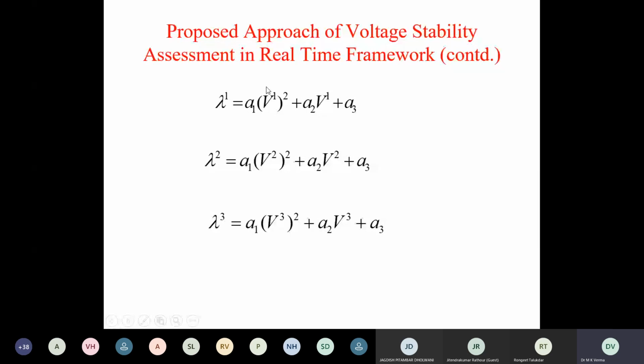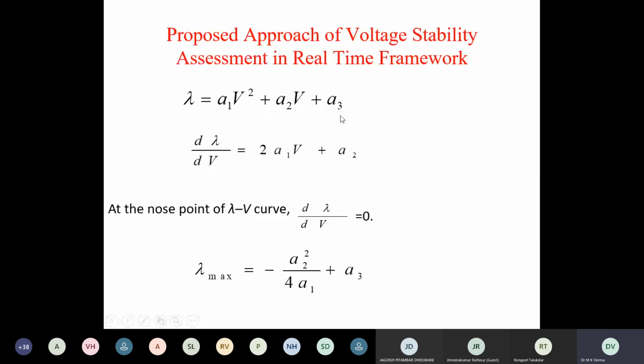Once these voltages V1, V2, V3 are measured by PMU, and these are loads at which voltages were measured, we get 3 equations in terms of 3 unknowns A1, A2, A3. That was solved to evaluate the constants. And once constants were evaluated with PMU measurements, lambda max was estimated. That gives voltage stability margin. So he calculated this voltage stability margin for the system in base case as well as critical contingency cases. Critical contingency here is identified based on voltage stability margin.